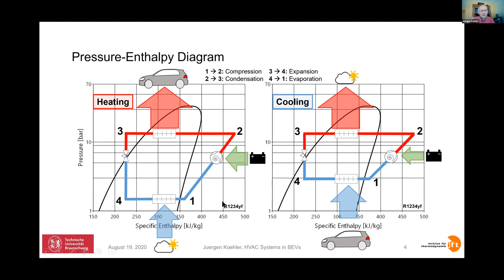I should mention one important thing: both cycles, both modes, look pretty much the same. However, there is one difference - the pressure on the low pressure side for the heating mode is much lower than for the cooling mode. This affects the efficiency and the capacity, and might even cause challenges if this pressure goes below 1, meaning below atmospheric pressure. I will get back to that later.